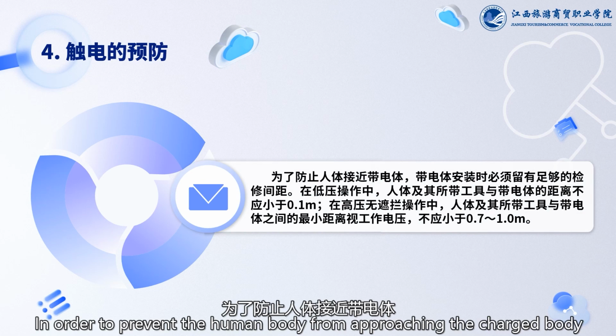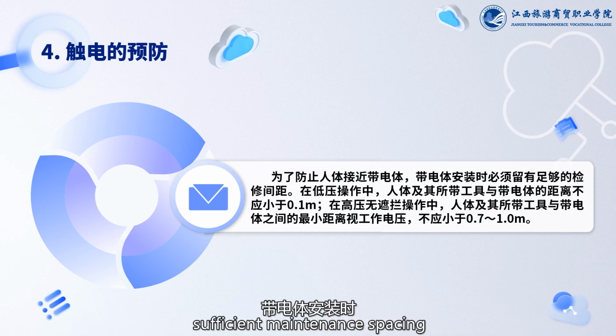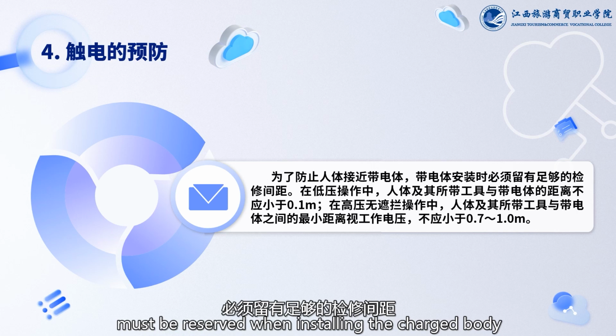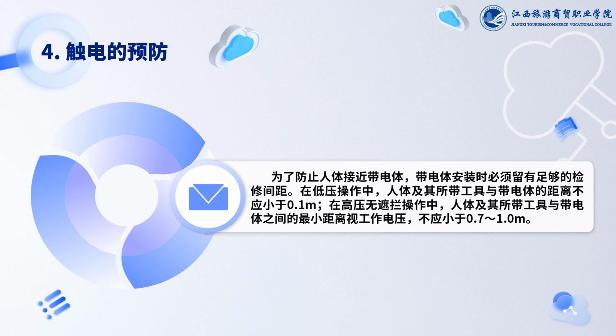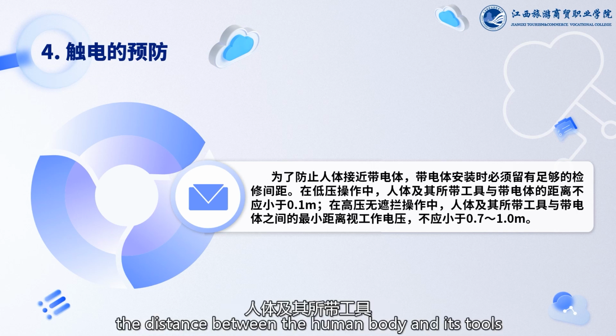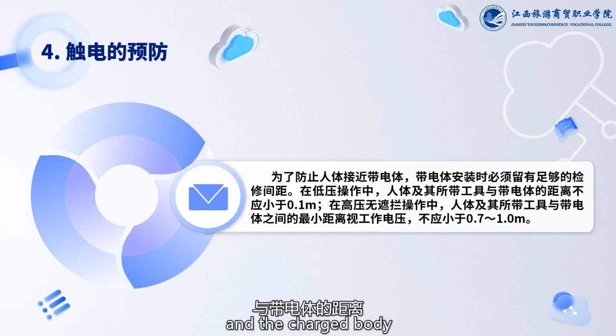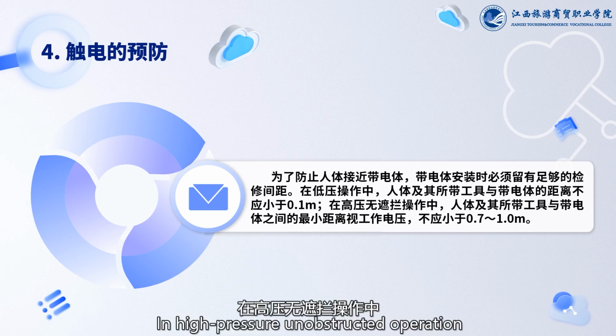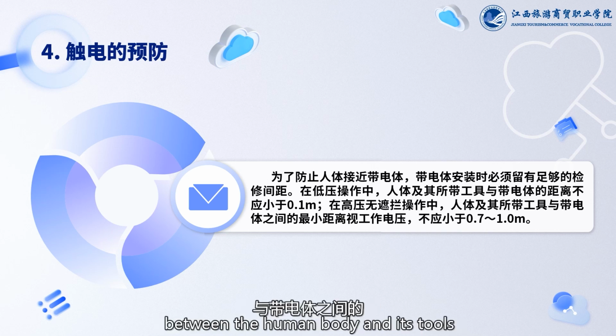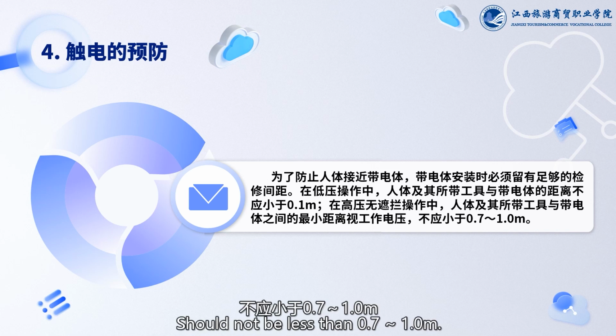In order to prevent the human body from approaching the charged body, sufficient maintenance spacing must be reserved when installing the charged body. In low-pressure operation, the distance between the human body and its tools and the charged body should not be less than 0.1 meter. In high-pressure, unobstructed operation, the minimum distance between the human body and its tools and the charged body should not be less than 0.7 to 1 meter.